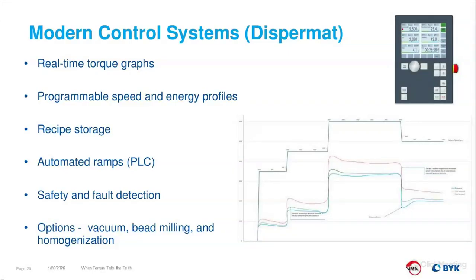It allows you to set every stage with your time, the amount of energy you put in, the RPMs, and it will automatically adjust throughout the process by itself, with the PLC controller. So it's a great function. It is an added cost. In a lot of cases, customers think it's worth it. In a lot of cases, customers don't think it's worth it. So I'll let you decide, but that functionality is an excellent way to take away any kind of human touch with regard to automatically producing these products.